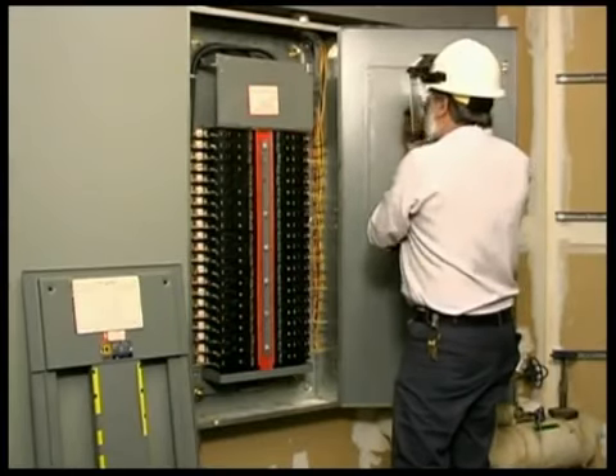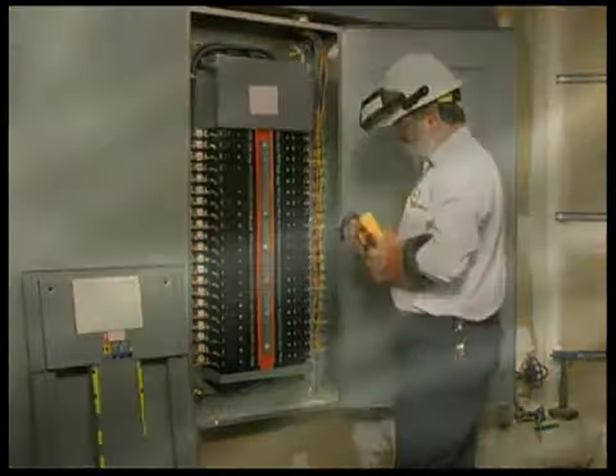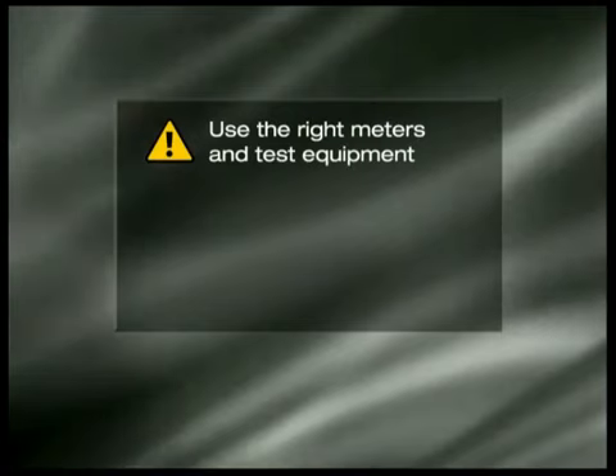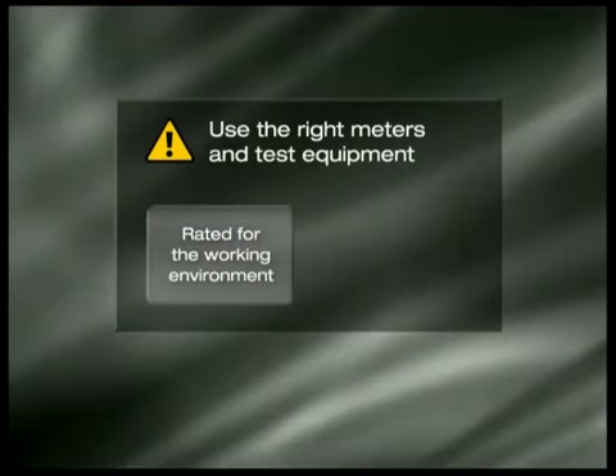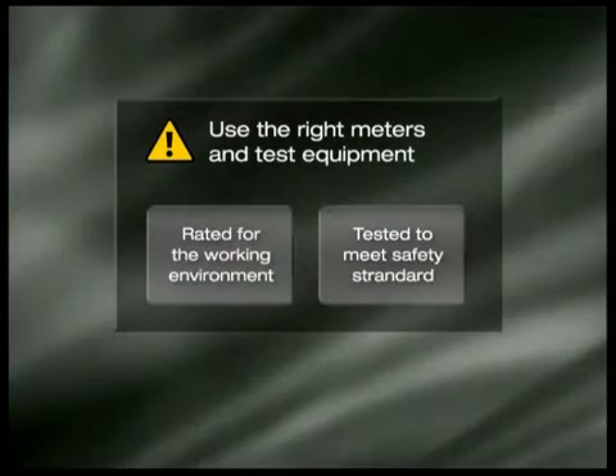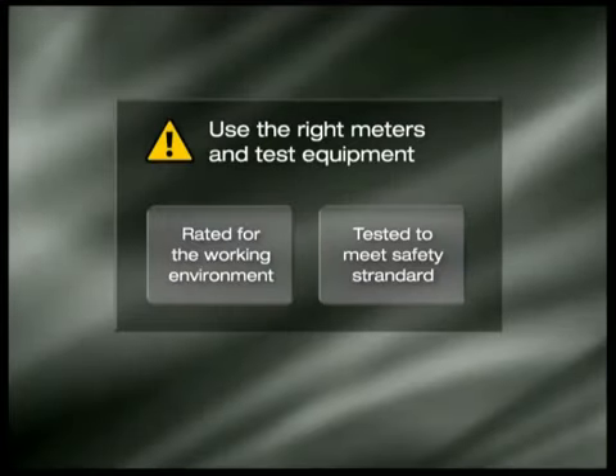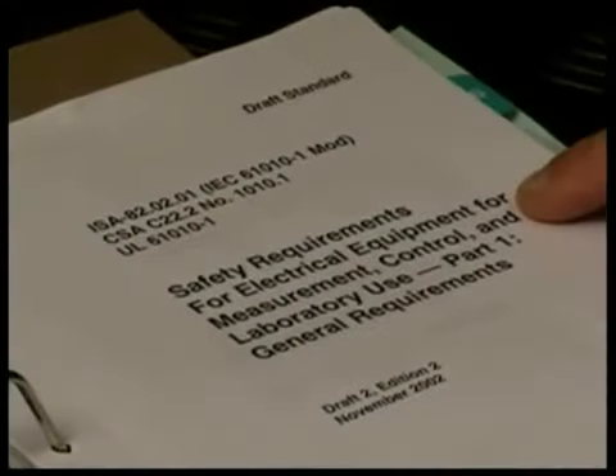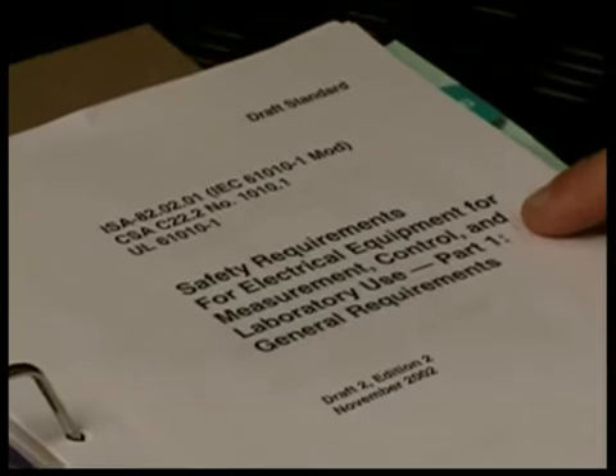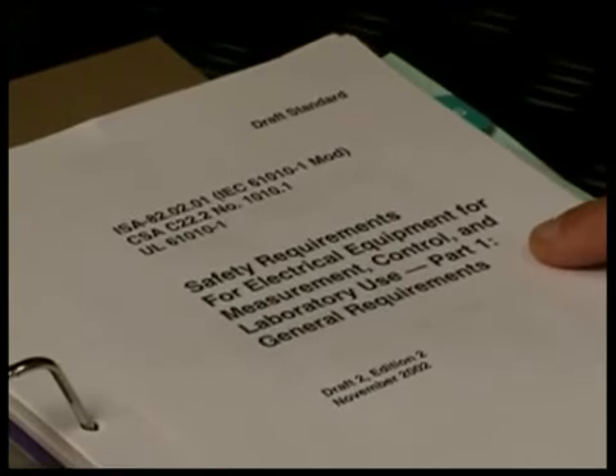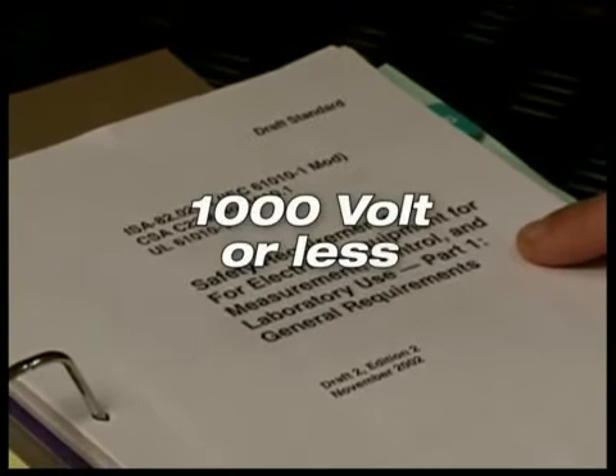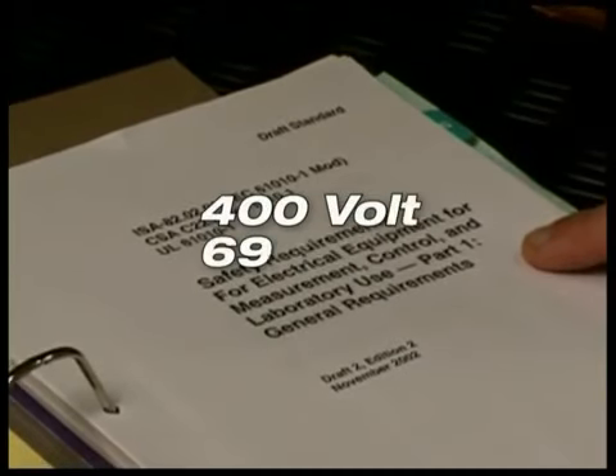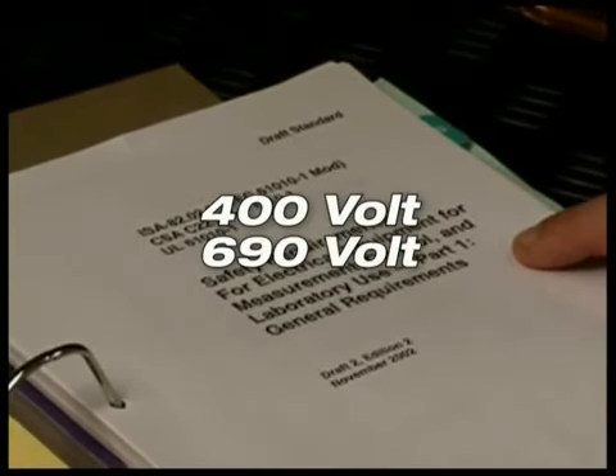Under these circumstances, proper procedures alone are not enough. You need to reduce risks by using the right meters and test equipment, tools rated for the environment where you are working, and tested to meet the appropriate safety standards. To provide better protection for electrical workers, new standards have been developed for test equipment used in environments of 1,000 volts or less, including 400-volt and 690-volt three-phase circuits.